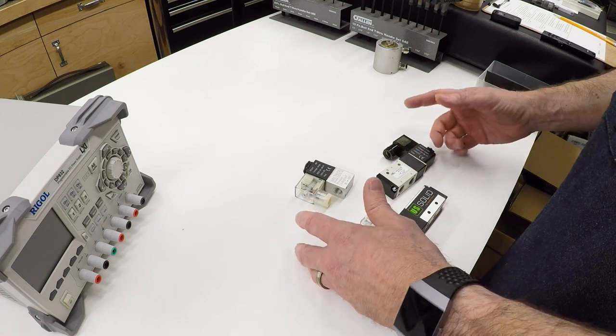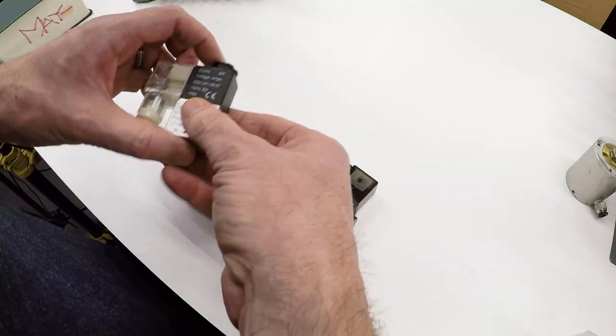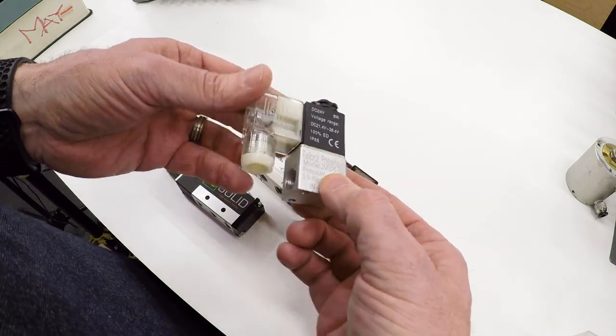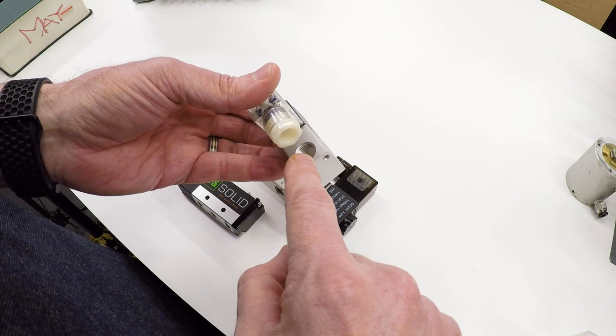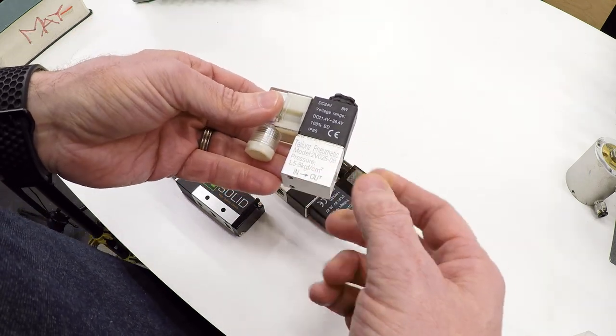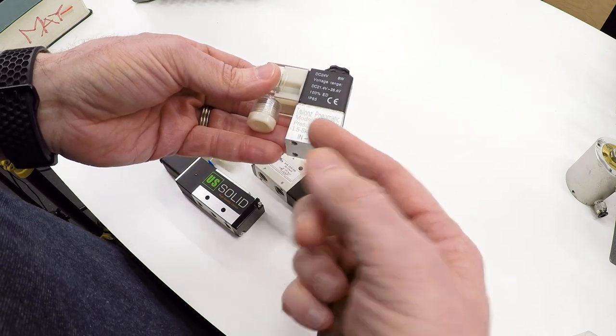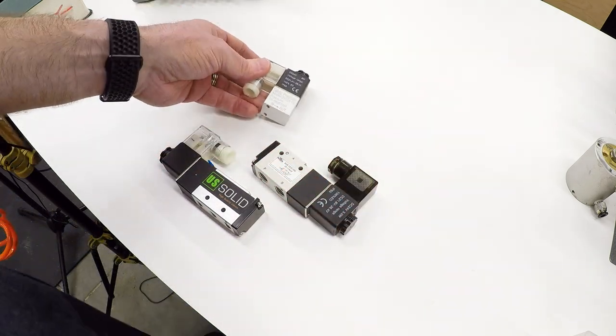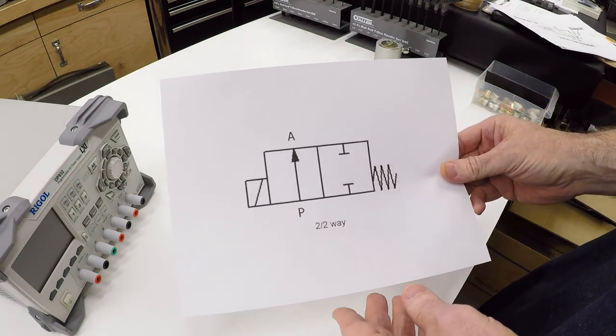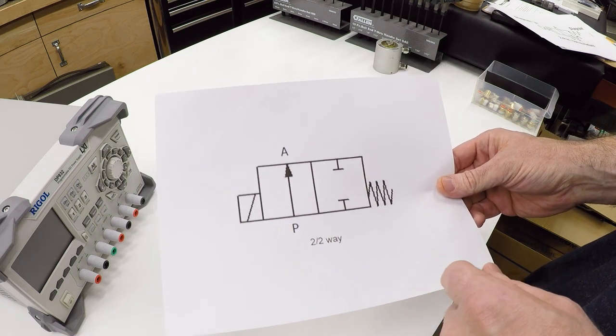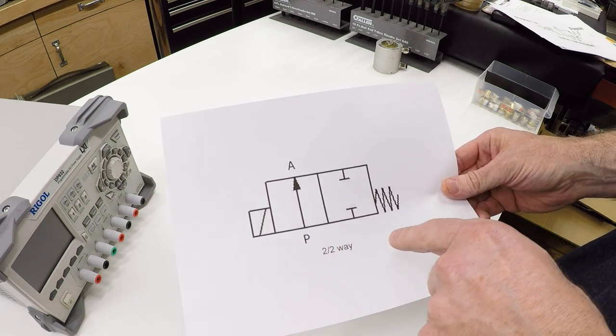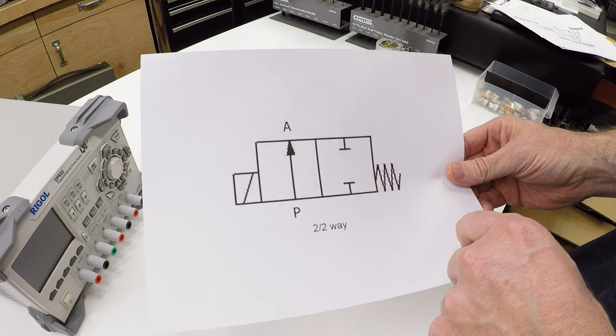There are three basic types that you will run into. The first one is what's commonly referred to as a 2-2 valve, and that means it has two ports, an inlet and an outlet port, and it has two positions. In the case of a 2-2 valve, it's either on or off. Every valve should come with a diagram that describes the functionality of the valve.